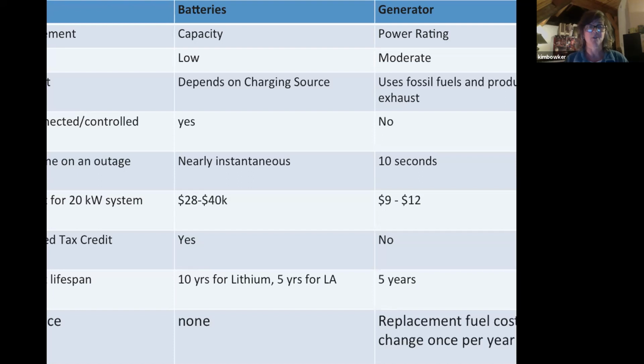I stole this chart from someone, these are not necessarily set-in-stone numbers. But if you do that math, you can see your generator over 10 years is going to cost you 18 grand, 9,000 for your generator times 2. And your batteries that cost $28,000, you're going to get a rebate, so they're going to be more like 21,000. So now over 10 years, not much of a cost difference.